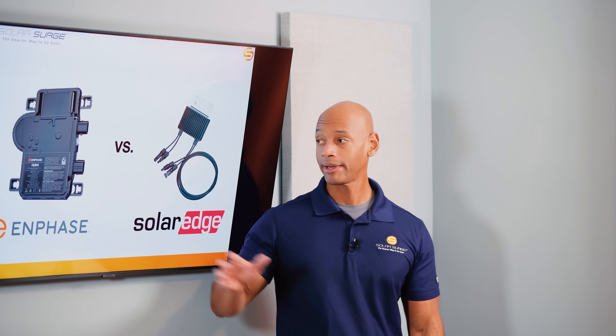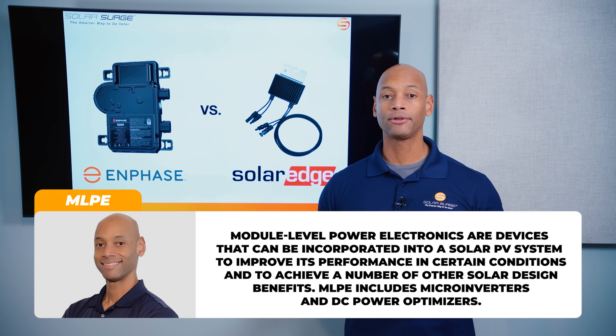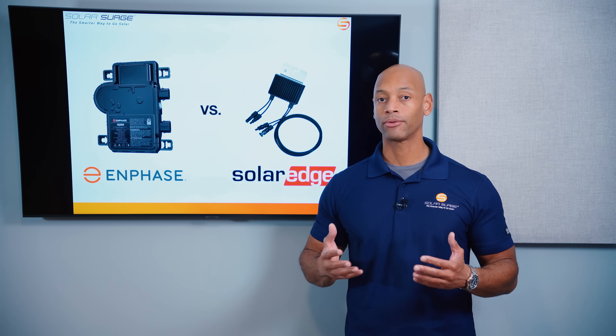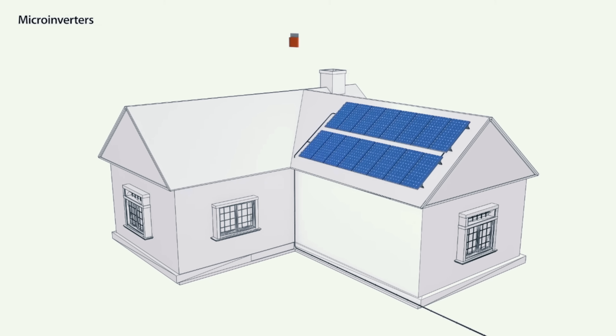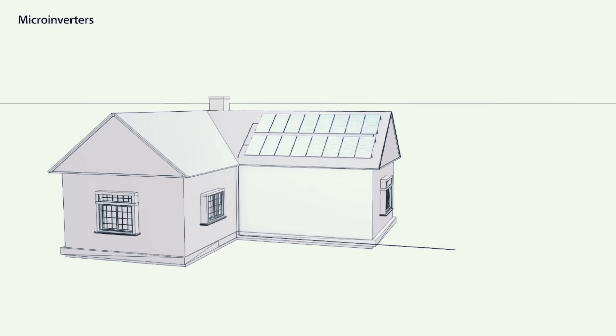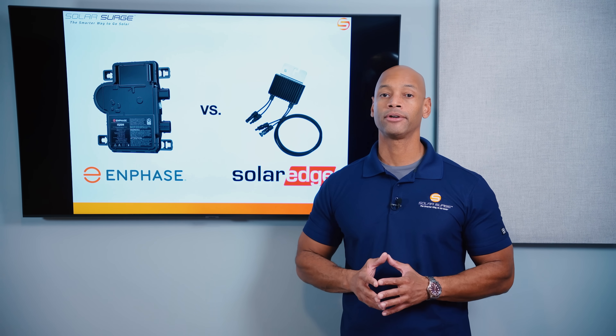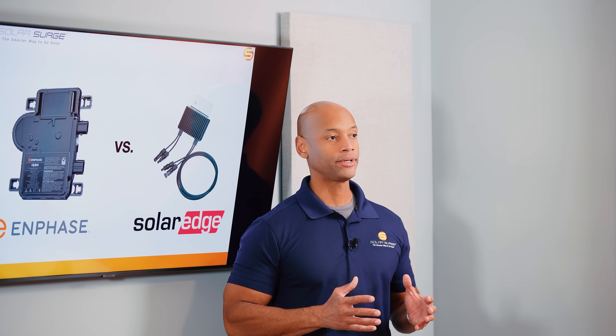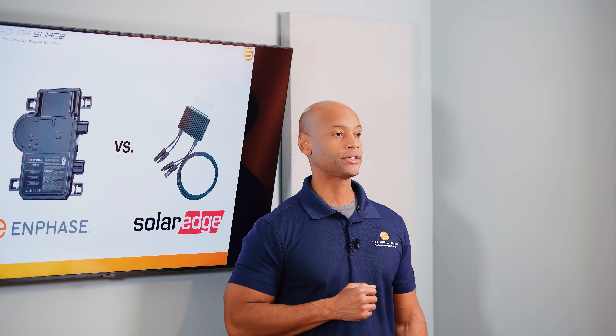Module level power electronics includes micro-inverters or DC optimizers. Both devices allow each solar panel to operate mostly independently at its own maximum power potential, so even if one panel is negatively affected by shading or damage, the rest of the panels can still operate at or near max power. The micro-inverter solution places a small inverter underneath each panel, doing direct DC to AC conversion on the roof, and the aggregate output is connected via a trunking cable to bring usable AC power down to ground level. This also gives system owners per-panel monitoring visibility.